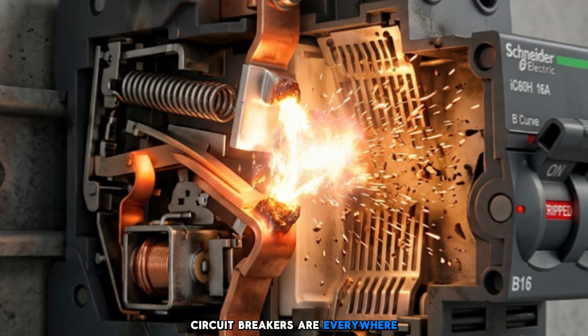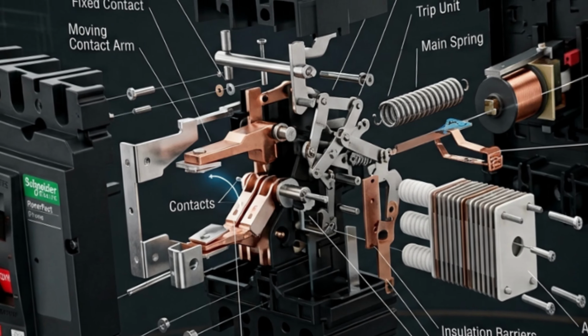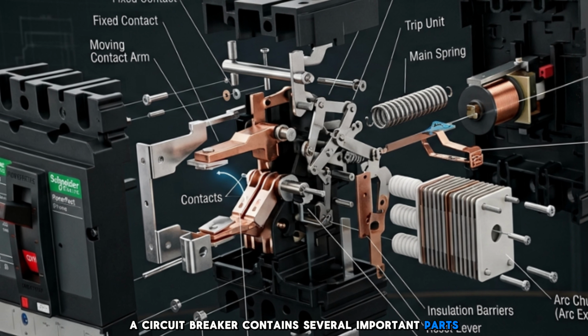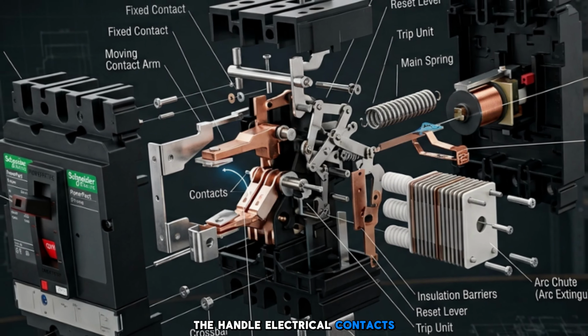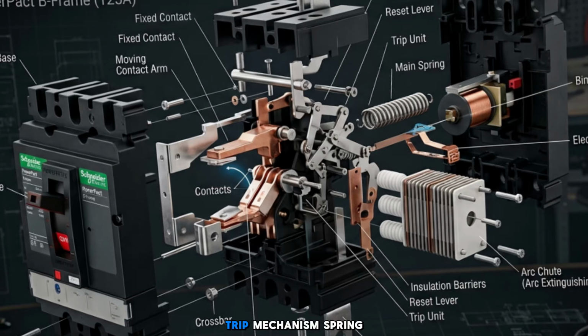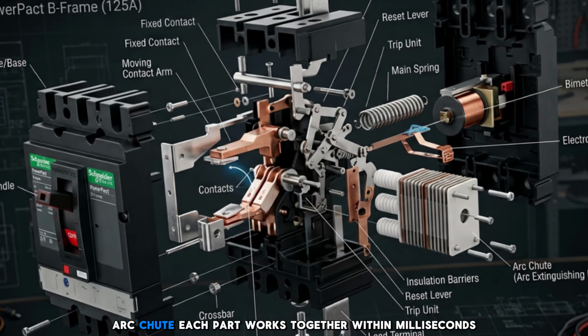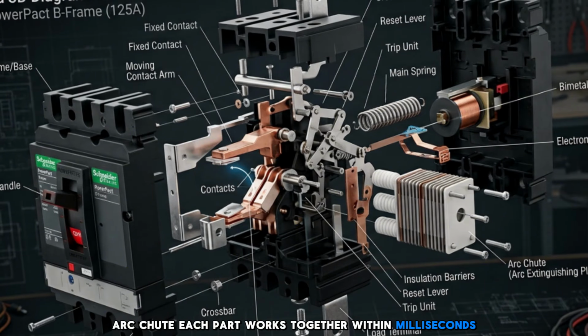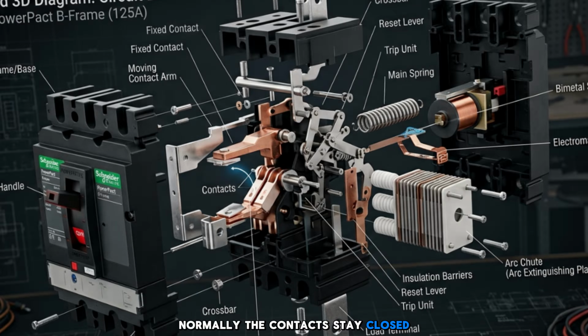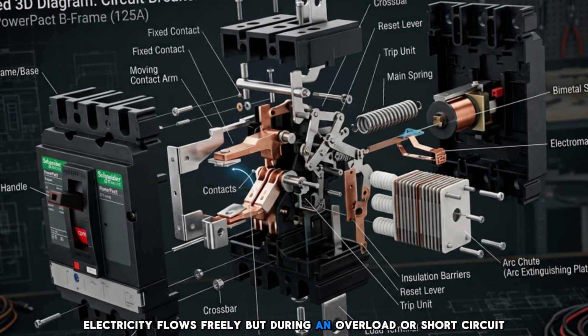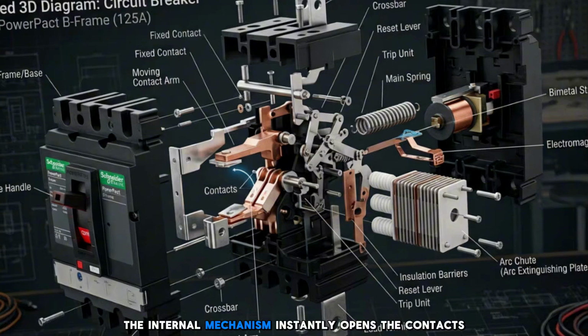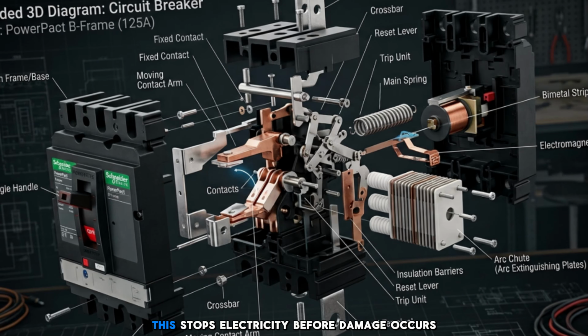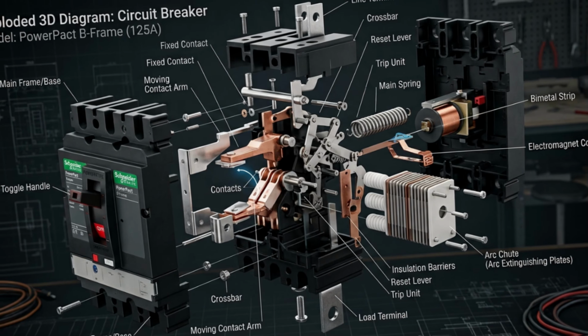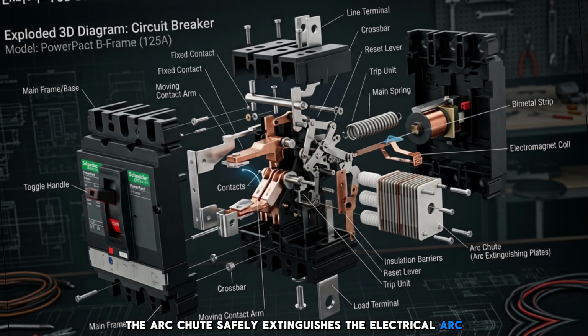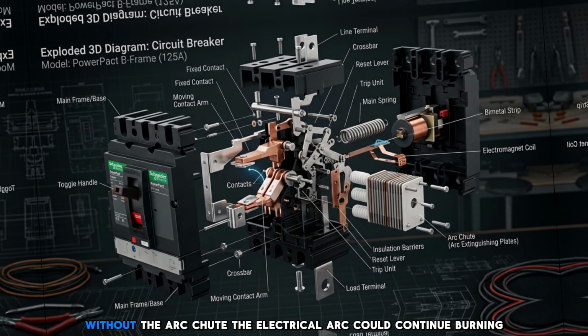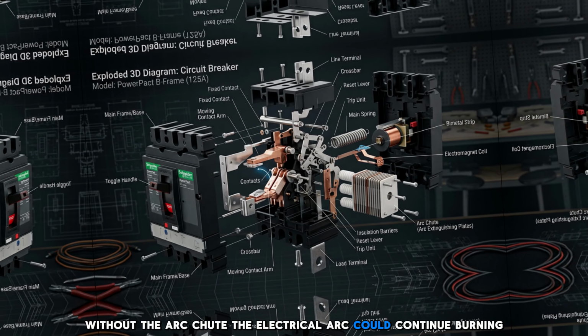Circuit breakers are everywhere. Although it looks simple from the outside, a circuit breaker contains several important parts: the handle, electrical contacts, bimetal strip, electromagnet, trip mechanism, spring, and arc chute. Each part works together within milliseconds. Normally, the contacts stay closed. Electricity flows freely. But during an overload or short circuit, the internal mechanism instantly opens the contacts. This stops electricity before damage occurs. The arc chute safely extinguishes the electrical arc created when the contacts separate. Without the arc chute, the electrical arc could continue burning.